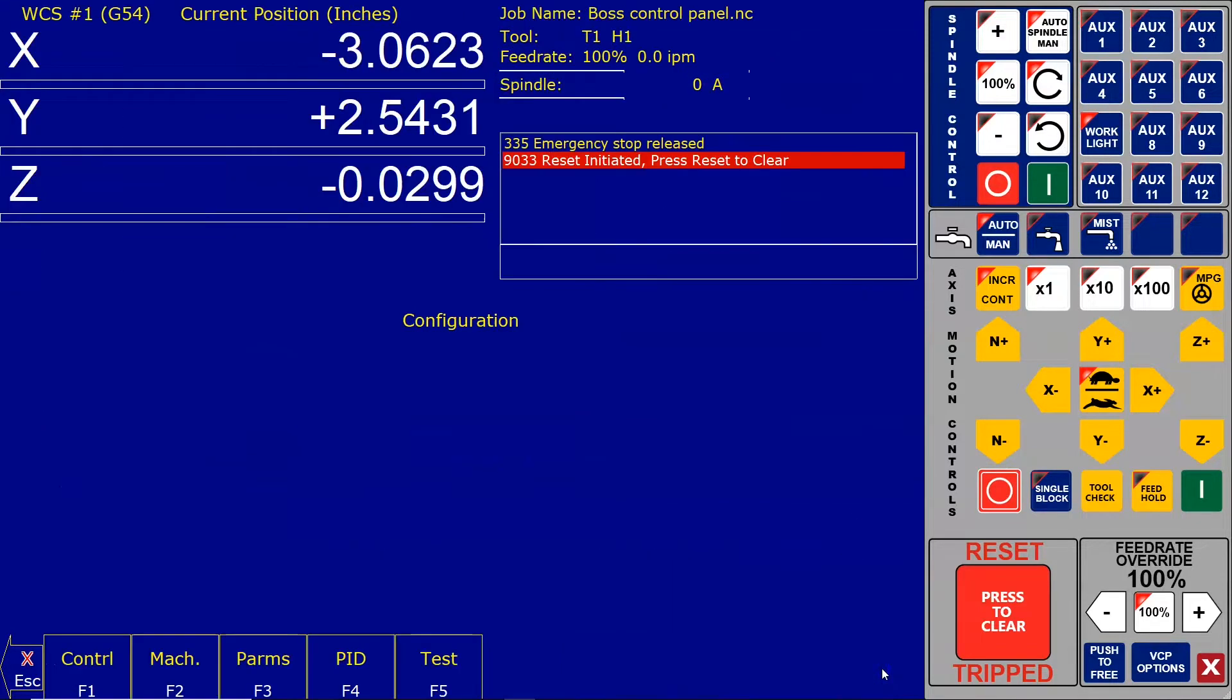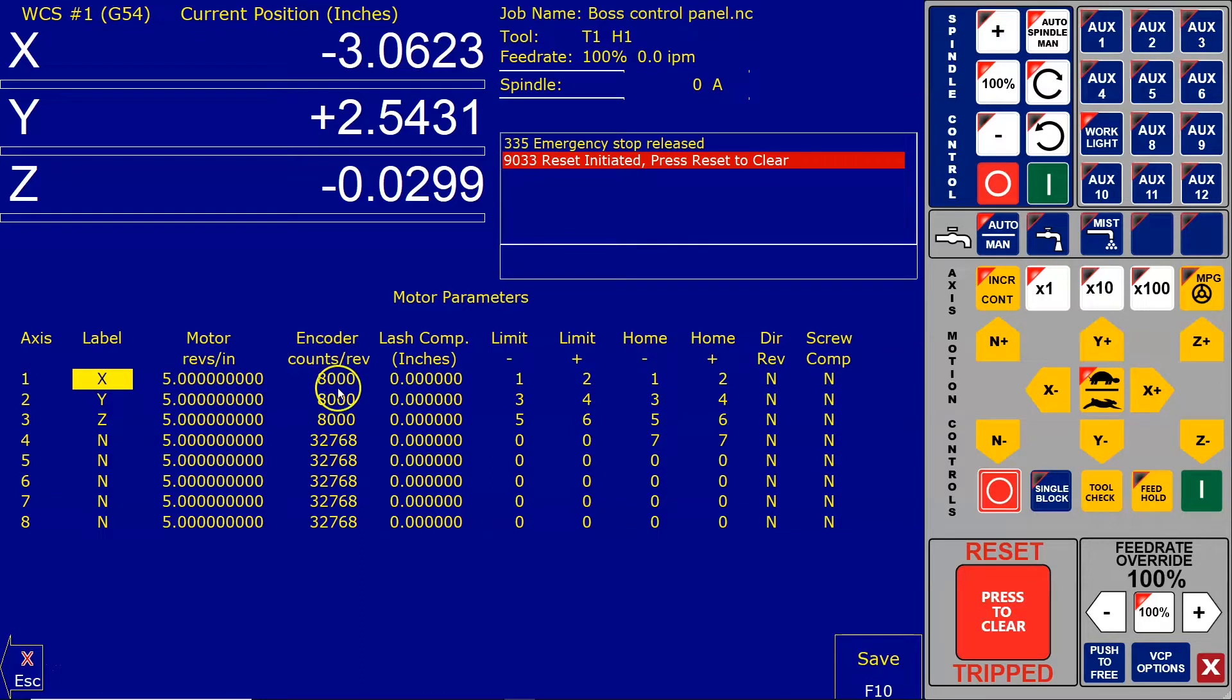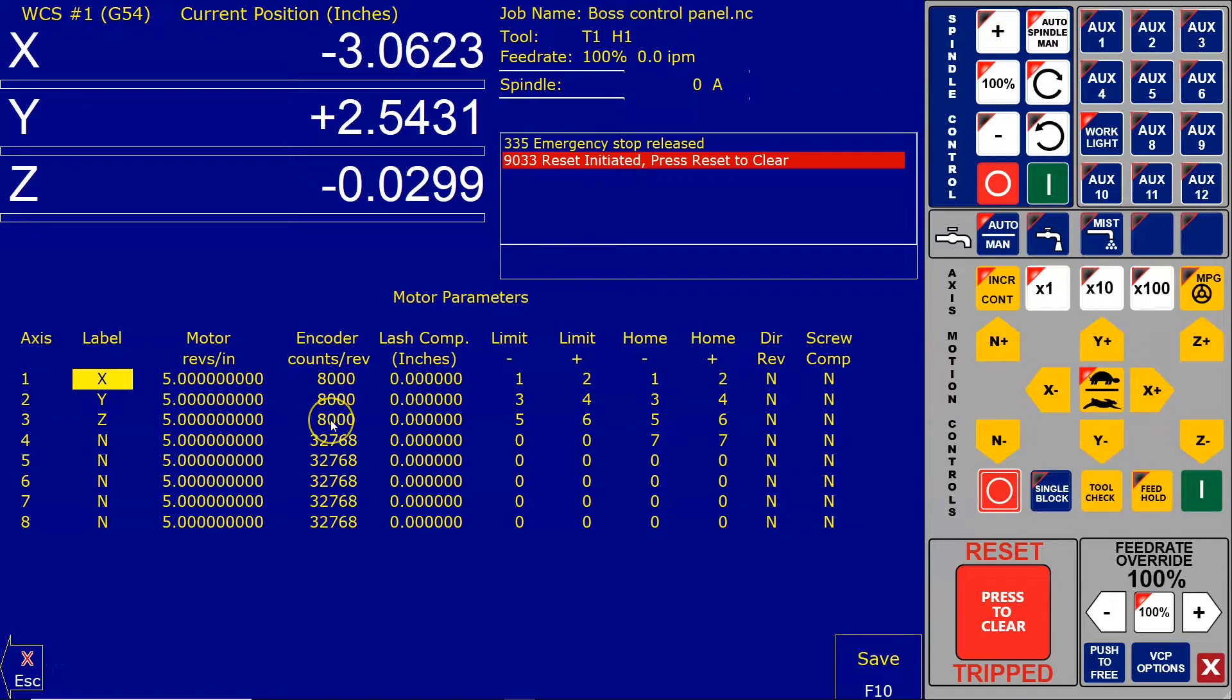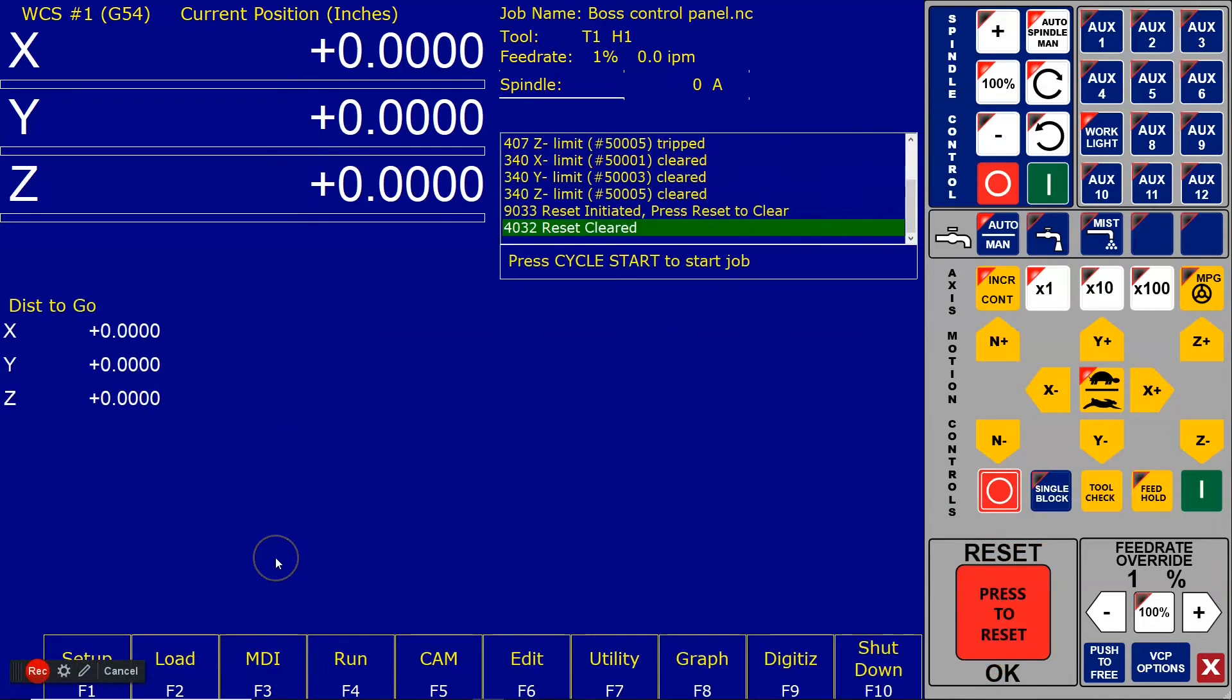Now we're going to go into Machine Motor. Since we set the line number to 2000, we multiply that by four and that becomes our encoder counts per rev. You can see I have them set to eight thousand. The three axes are set to eight thousand, so we save it.